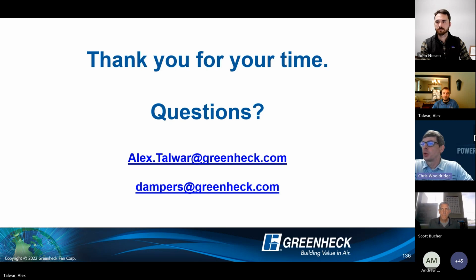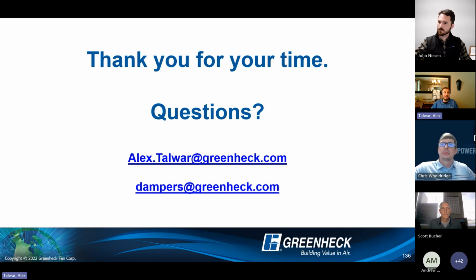Thanks, Alex. I think we did have one more question here. One of the challenges we have is achieving airflow when the designer doesn't know or understand the difference between net and free area, in particular with smaller FSDs, hoping there's some awareness being shared. So not necessarily a question, but it's a good matter of fact statement, right? 100%. You're worried about free area and pressure drops and restrictions on airflow. 100%. So that's a good thing if you're talking to Chris and looking at Greenheck, because we're well aware of that.